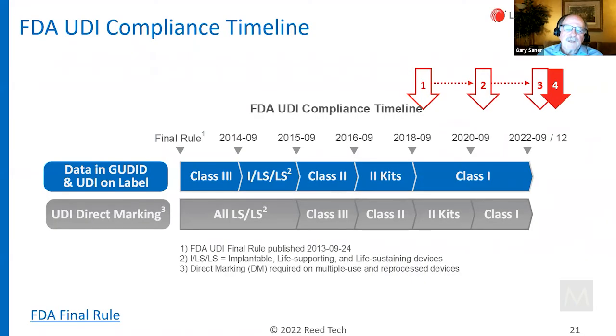And then secondly, I would go to this global database and at least find that this particular number has been recorded and properly approved by the FDA. And then thirdly, it becomes an issue if your number is not up there. It's highly suspect that this is not a legitimate product. But then think about what we talked about earlier. If you're exempt and you did not put your DI in there, now the surveillance kind of doesn't have any verification tool. So all those reasons we talked about for voluntarily submitting, let's add counterfeiting to that list as well. So really good point.